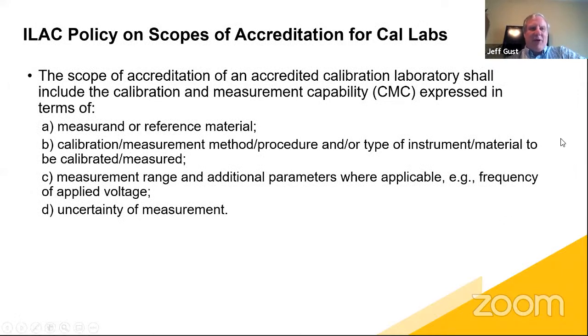So the ILAC policy on scopes of accreditation. This whole section talks about what goes on your scope of accreditation. So the scope of accreditation of an accredited laboratory shall include the calibration measurement capability, or CMC, expressed in terms of the measurand or reference material. So what are we trying to measure, like DC volts? The calibration or measurement method or procedure and or type of instrument to be calibrated or measured. So, we're doing direct measurements, or we're using X procedure, or we're calibrating DC voltage on voltage measuring instruments.